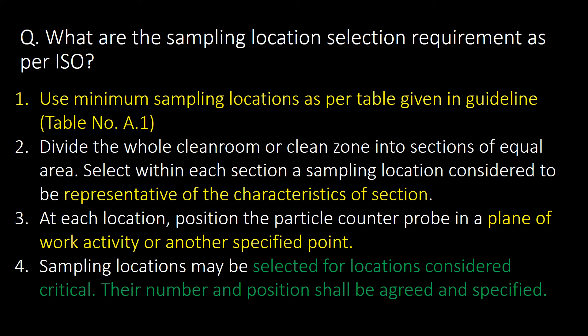Requirement three: at each location, position the particle counter probe in a plane of work activity or another specified point. Requirement four: sampling locations may be selected for locations considered critical — their number and position shall be agreed upon and specified.